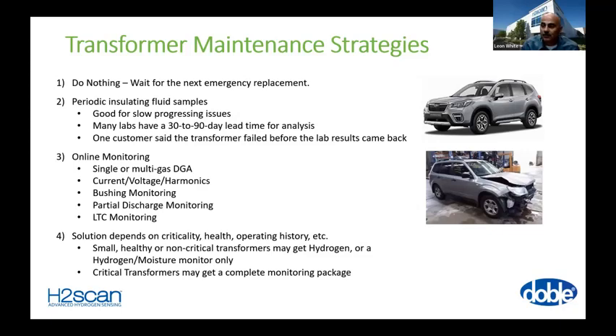If you're not treating your transformers properly, if you're not maintaining them, if you're not keeping the protection from letting the transformer see through faults, the more through faults, and especially the more significant through faults that they see, the less life you're likely to see from that transformer. So as Tony pointed out, through faults are a big issue, and protecting your transformers from through faults is very important. And so that goes back to Moses' presentation about making sure your protection schemes, your relaying and so forth, are properly maintained.